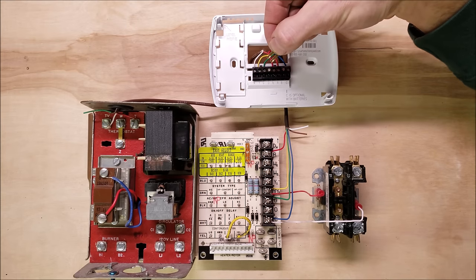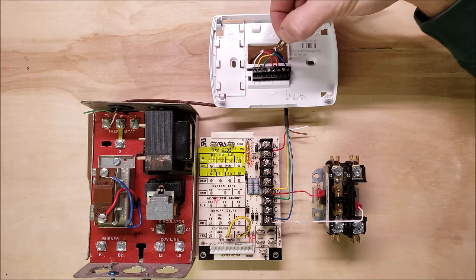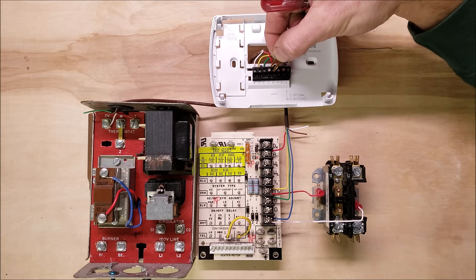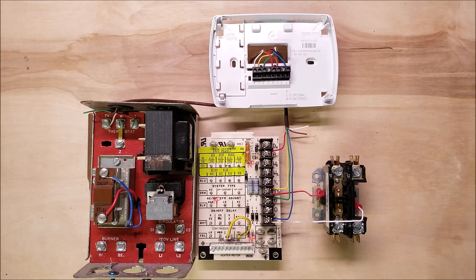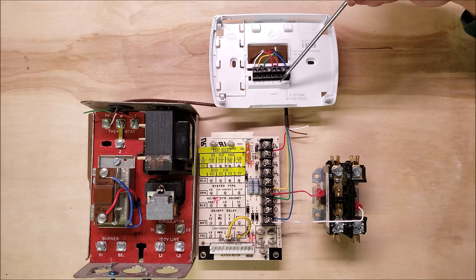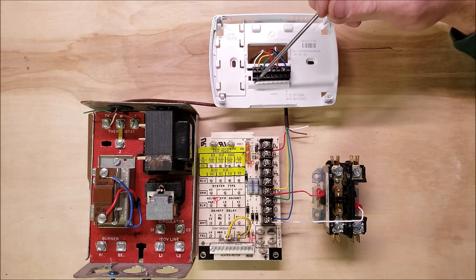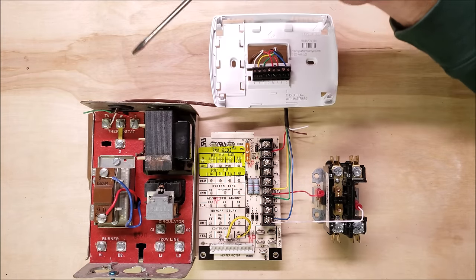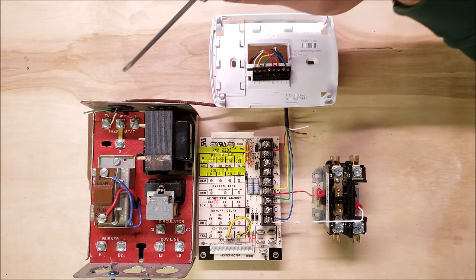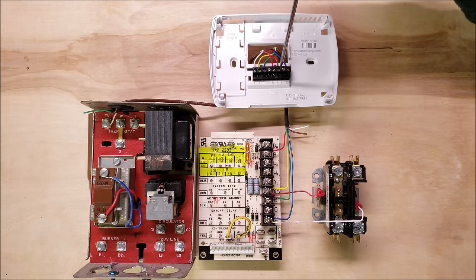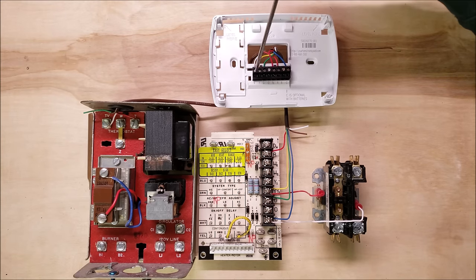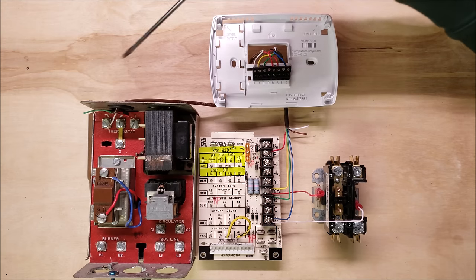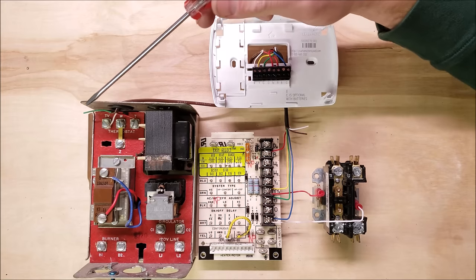Thermostats usually come with a little jumper between R and RC. The reason we can control two separate units is we pulled this jumper out. When we pull that jumper out, R is for your heat and W is where it sends the voltage back to the Aquastat. You have T, your red wire coming over to your R terminal, then it connects in the thermostat to W and comes back out W over to TV, turning on your circulating pump.